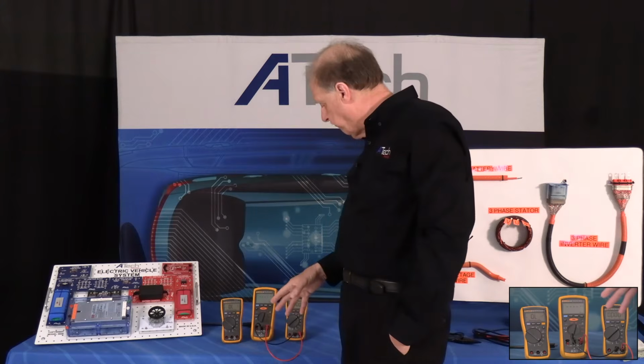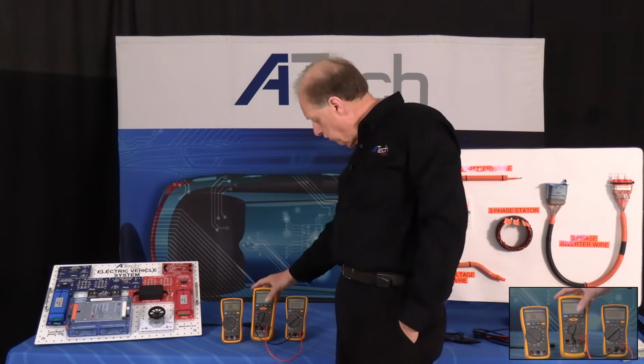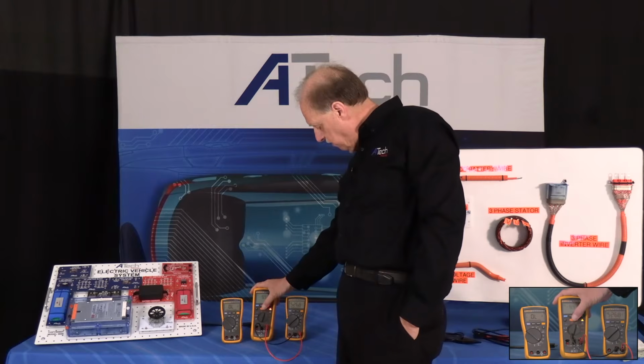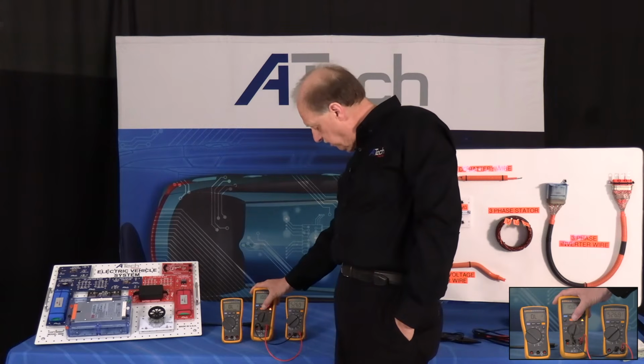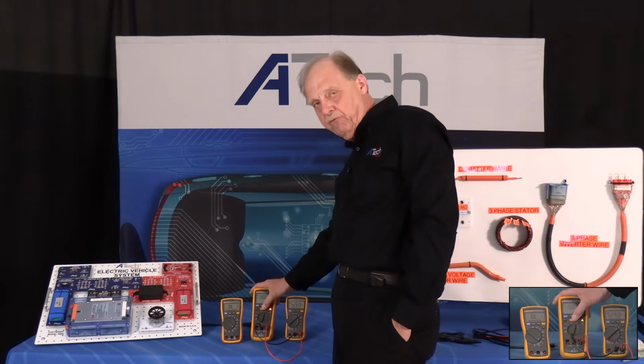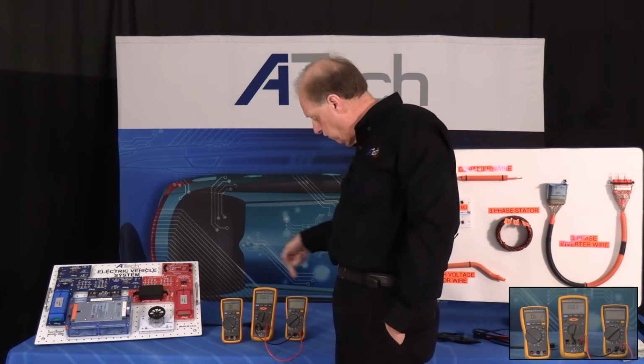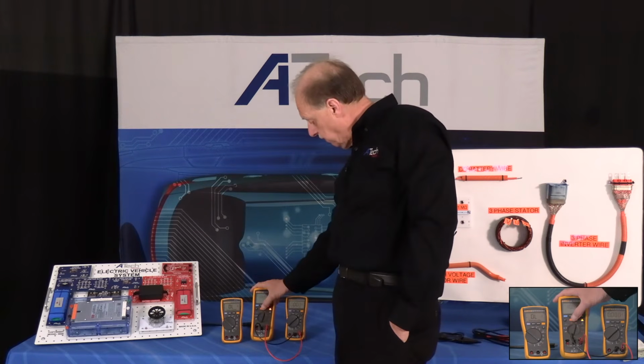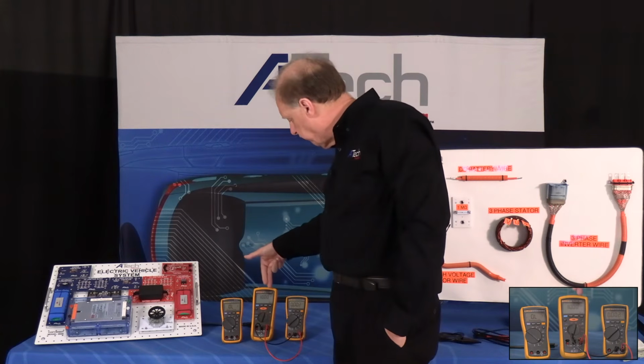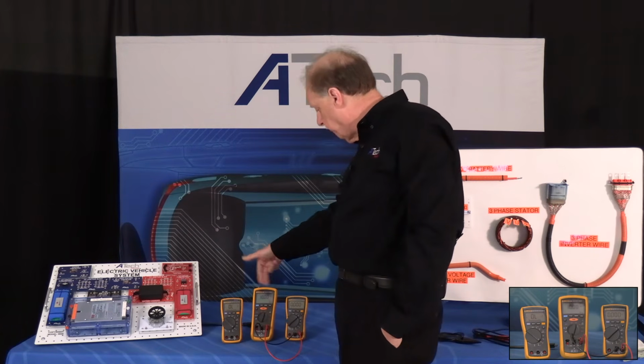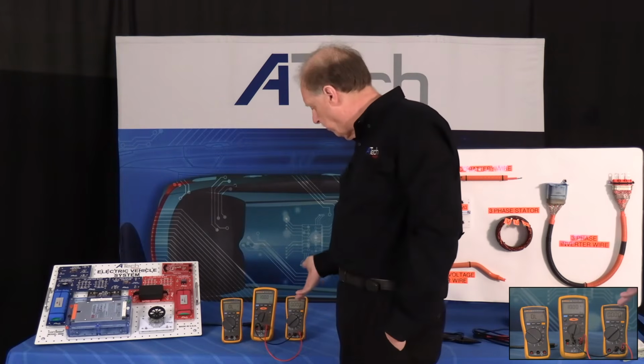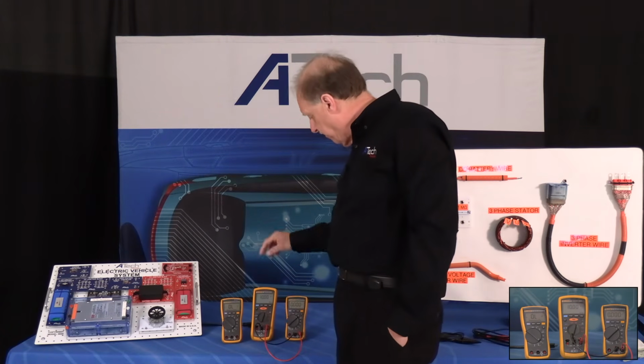So I'm just going to test the voltage output on this particular meter by pushing this down. And when I push it down, you'll see we got 526.9 volts. 500 volts is coming out of this meter over to here. When I let off, you're still going to see the 10 megohms up here in the process. It's actually measuring it, telling you what we've got. Now, that's at 500 volts.